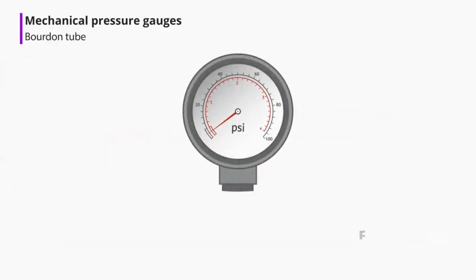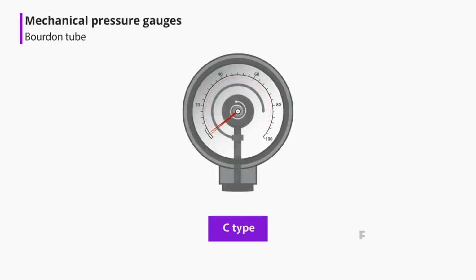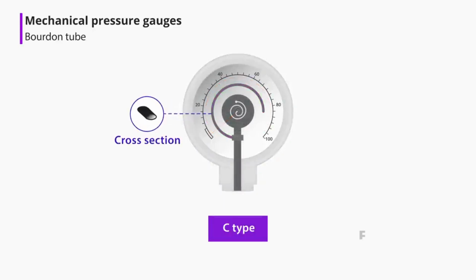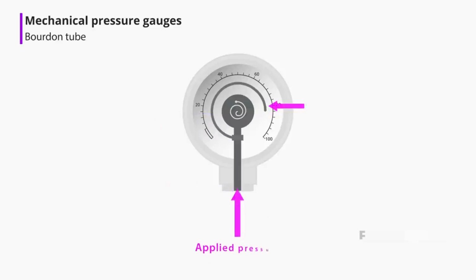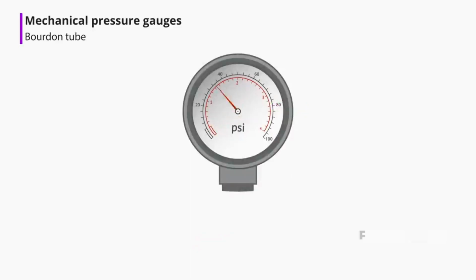Of those three mechanical pressure gauges, by far the most common is the Bourdon tube type. So let's have a closer look. The most common type of Bourdon tube gauge is the C type, in which the tube is shaped to resemble the letter C. Notice the cross-sectional shape of the tube. The tube is opened at one end and sealed at the other. A change in pressure causes a deflection in the tube that is proportional to the applied pressure. The actual movement of the tube is converted into a pressure indication on a calibrated faceplate. The maximum movement of the pointer is usually 270 degrees.